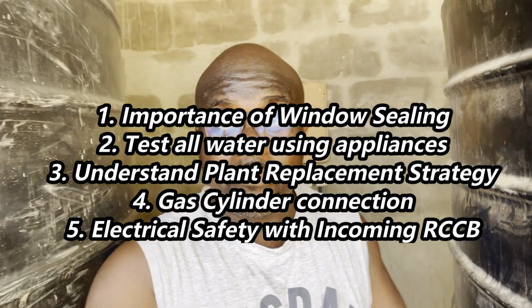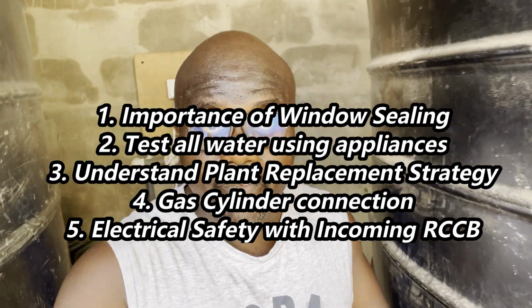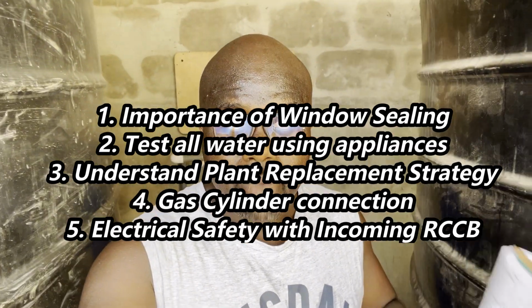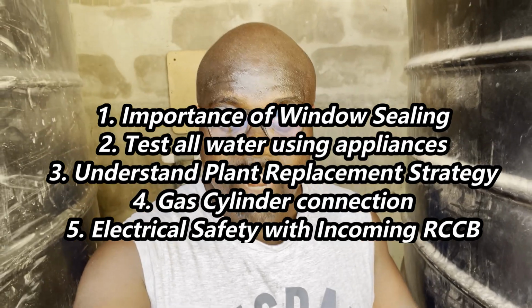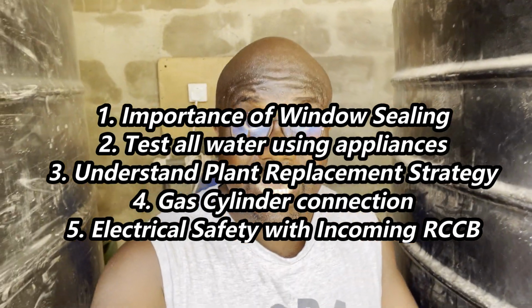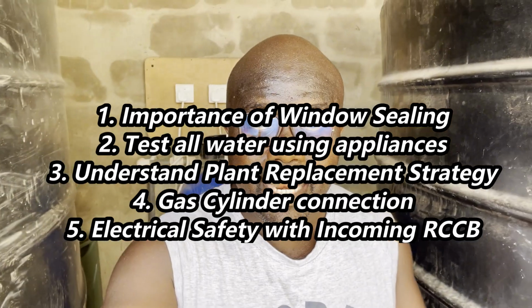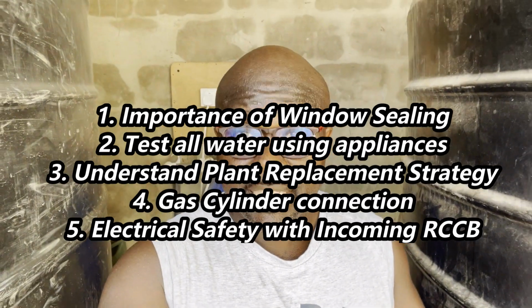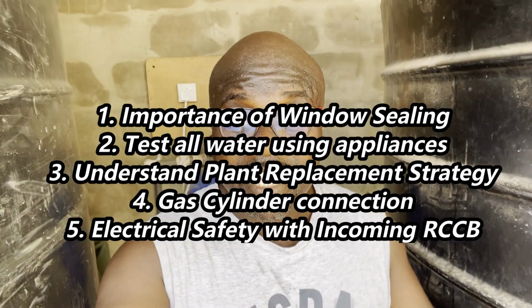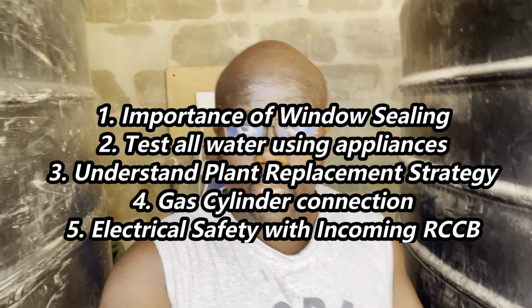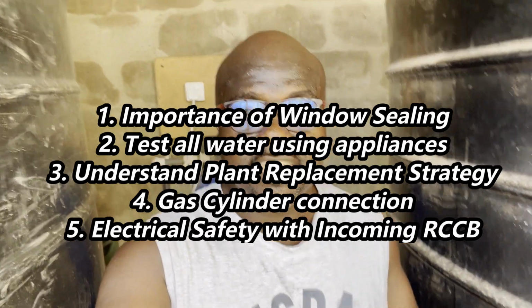And the last one, number 5, was the importance of electrical safety. It is a must in the electrical regulations of the TT Earth system, which is what you have here in Ghana for domestic premises, that you must have an RCCB on the incomer to your home. Ideally 100 milliamp sensitivity, but you can go to 200 milliamp as well, depending on the appliances installed in your home. You want to be safe, but you also don't want it to nuisance trip.